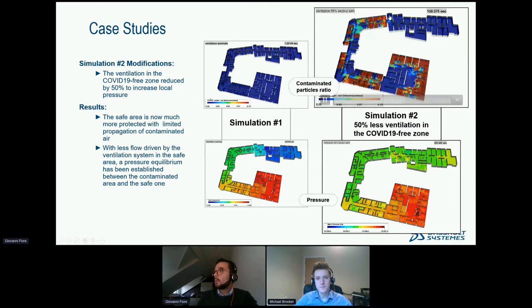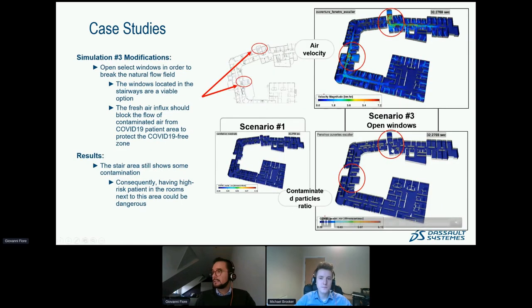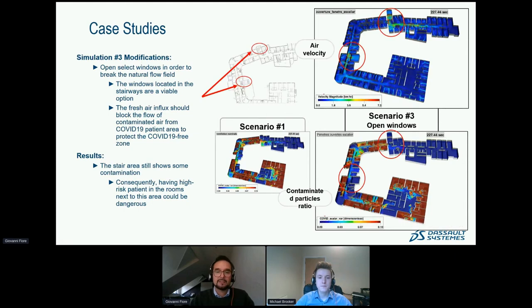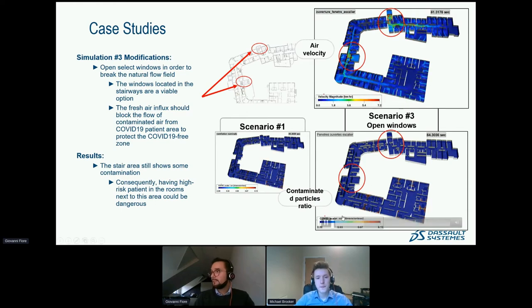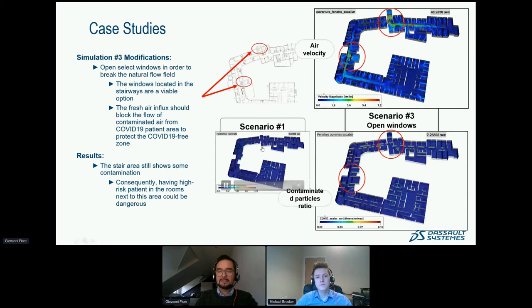The first suggested measure was reducing ventilation in the non-COVID ward, changing the pressure gradient from a steep red-to-blue gradient to a milder red-to-green gradient. This significantly reduced contaminant concentration at the interface. A third variant involved strategically opening windows in specific areas of the hospital, which also produced a greatly reduced spillage of contaminant from the COVID ward to the non-COVID ward.